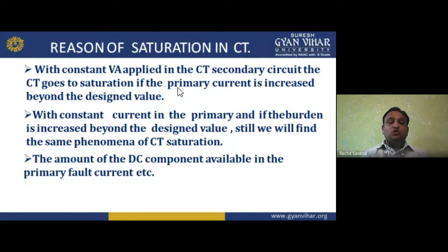Effect of saturation on metering and protective current transformers. Once the CT is saturated, it will not be able to reproduce the secondary current in proportion to its primary current. Hence the relays connected to the CT circuit may malfunction and give undesired output. The circuit may malfunction indiscriminately and trip the circuit. It gives the input to the circuit breaker, and the circuit breaker will break the circuit not as desired, operating even when no fault is occurring.